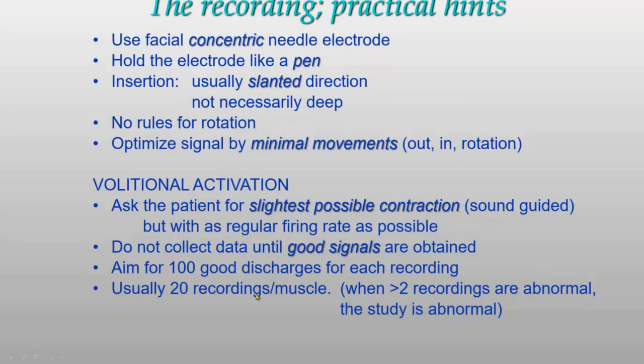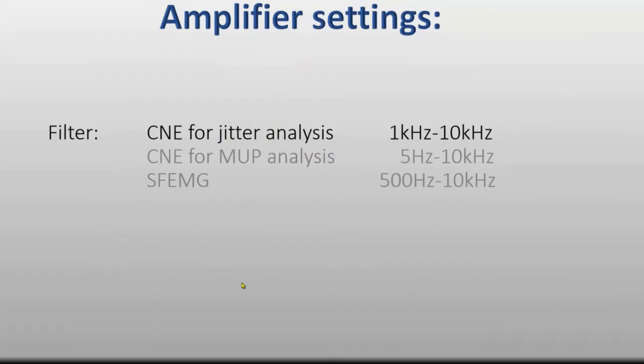Usually we record from 20 different positions in the muscle, which includes about two skin insertions. The amplifier filter setting is 1 kHz to 10 kHz — in single fiber EMG it was 500 Hz, but here we use 1 kHz as the lower limit.